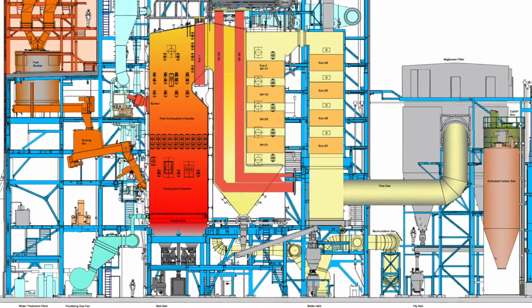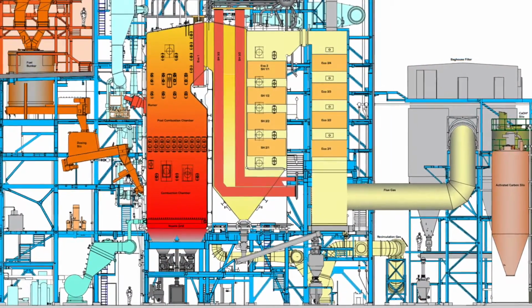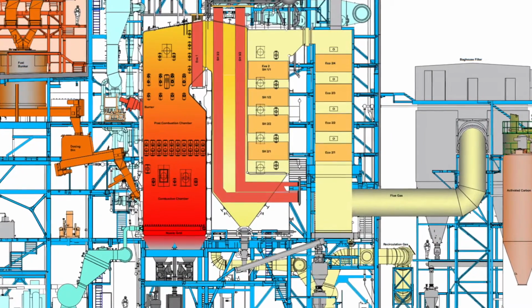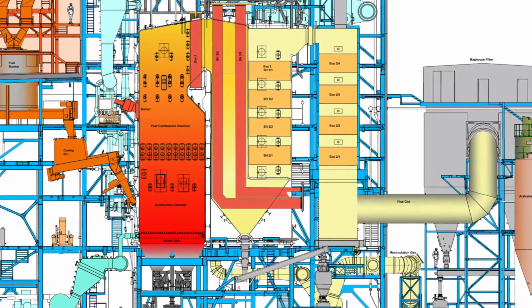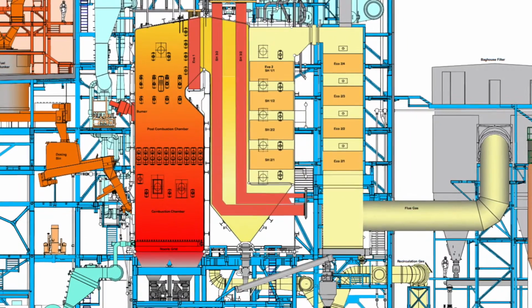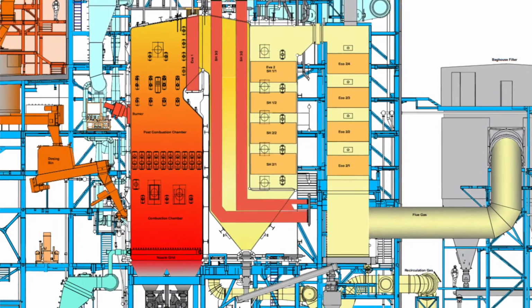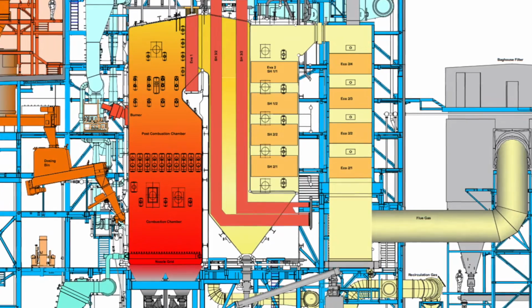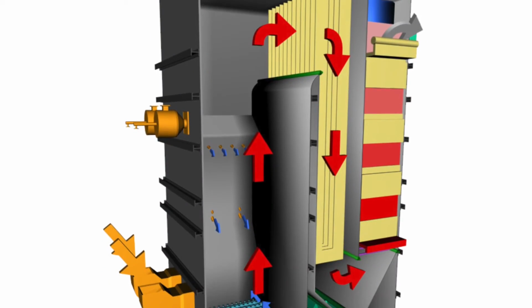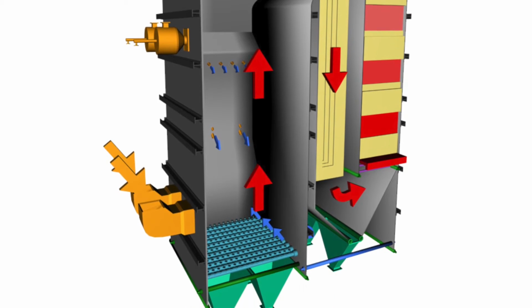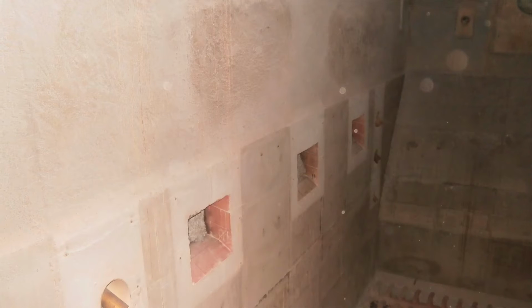The steam generator is a bottom-supported 3-pass type with natural circulation, where 3 passes are integrated in the evaporator water walls. The economizers are located in the 4th pass. The bubbling fluidized bed is situated in the lower part of the first boiler pass. The water walls in the fluidized bed area and a part of the post-combustion chamber are covered with refractory material for erosion protection and thermal reasons.